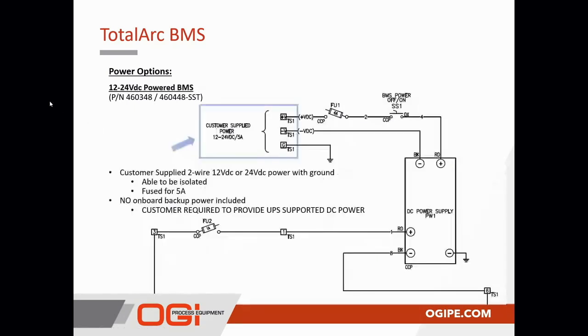The last option that we have associated with power options is the 12 to 24 volt powered BMS. Now, this again is something where the customer is providing the power. In this case, we're looking at the customer to provide a 2-wire 12 to 24 volt DC power system with ground to the terminals within the BMS panel. Again, they need to be isolated. And in this case, instead of it being a 10 amp service, we're looking only for 5 amps.